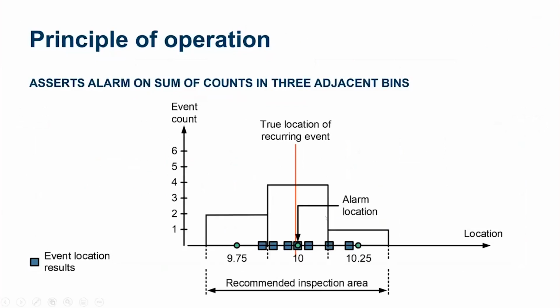And so now we've got these three bins here, and we've got four traveling wave precursors that were detected. What we can do is alarm at this location. We can tell the crews, hey, we've got a problem here at this section of the line at mile 10. This is the true location. You should check a quarter mile behind and a quarter mile ahead of that fault point. All right, so that's all I have for our transmission line wildfire mitigation.